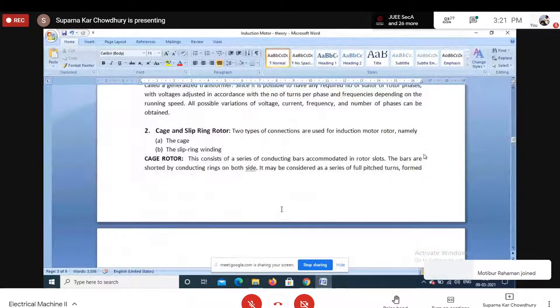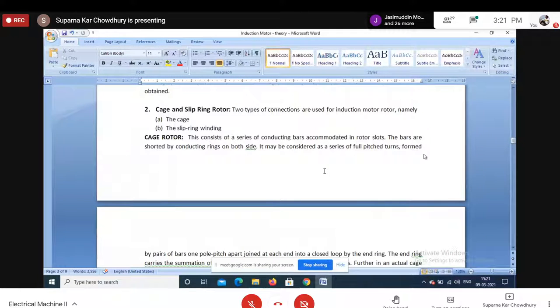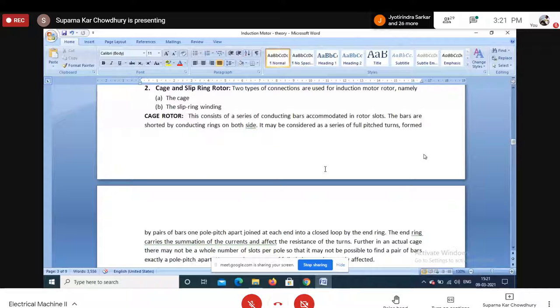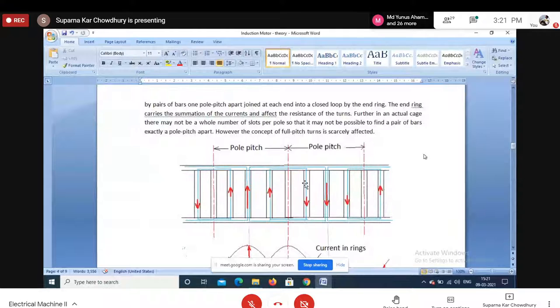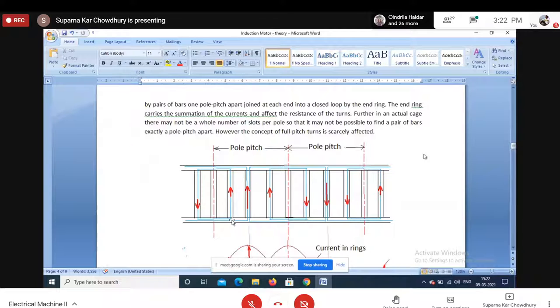On the rotor, we can have two types of winding — a cage rotor or a slip ring rotor. In a cage rotor, aluminum bars (or now also copper bars) are placed in slots and shorted on both sides by end rings, forming a squirrel cage. Copper cage rotors offer smaller machine size and higher efficiency since copper is a better conductor, though copper welding is more difficult.